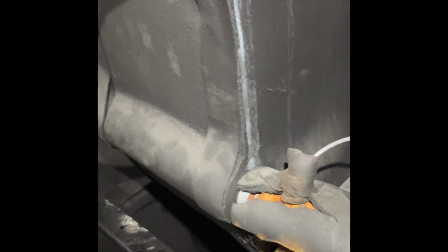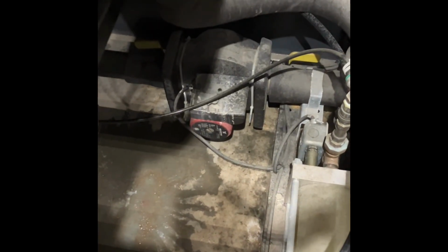ends up back in the return tank here, and then that glycol is pumped through the air to glycol heat exchanger here, and then like I said, the glycol will end up back in the tank there. And that's how a Zeks dryer works. So it's not a direct air to refrigerant type heat exchange. So the refrigeration system cools the glycol, then cools the air, and then returns to the tank. That is all done by means of that little glycol pump right down there.